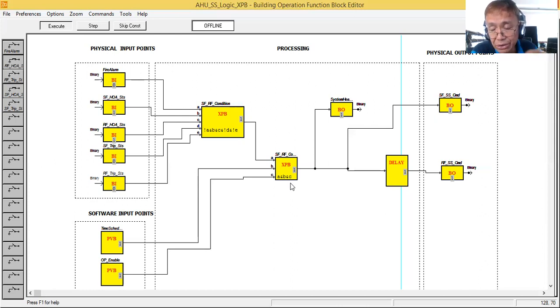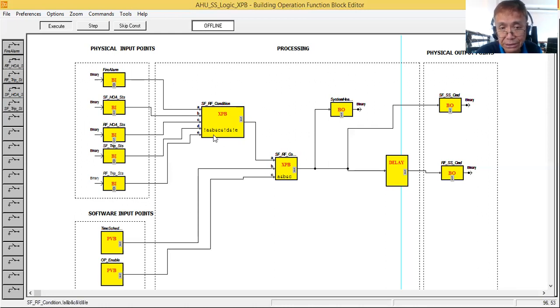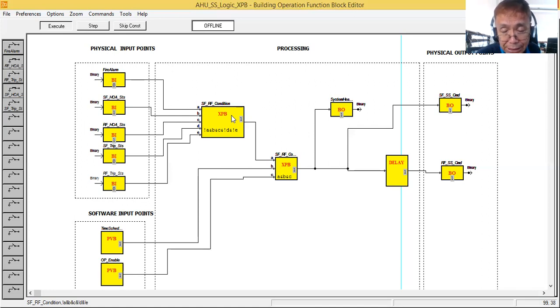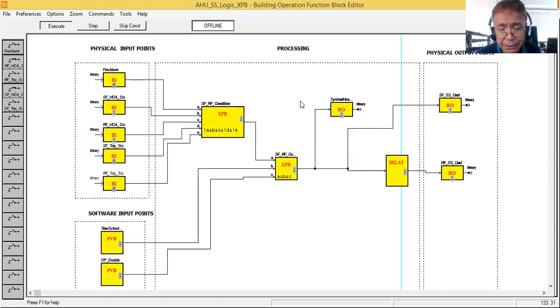This is a different approach to programming the fans of an air handling unit. The first approach uses a combination of logic gates — AND, OR, NOT. If you want to avoid that combination of gates, you can use an expression block as shown here. Just be very careful writing your expression, and know whether to use expression block binary, integer, or real. For binary, conditions must be written in small letters.